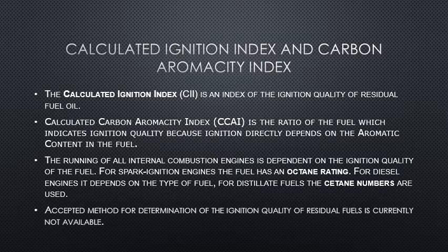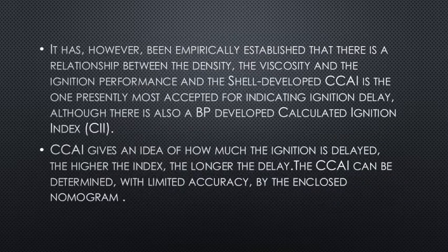An accepted method for the determination of the ignition of the residual fuel is currently not available, but it has been empirically established that there is a relation between the density, the viscosity, and the ignition performance, and the Shell-developed CCAI is the one presently most accepted indicating ignition delay. Although there is also the calculated ignition index that we are discussing right now.